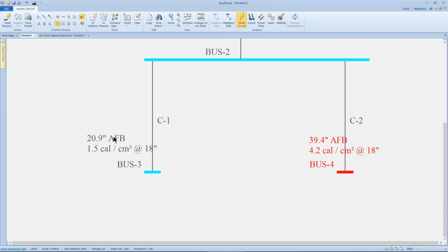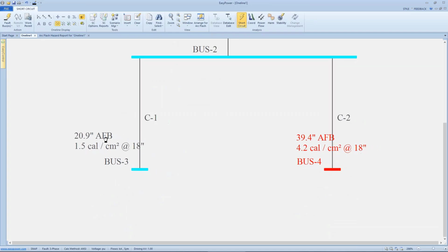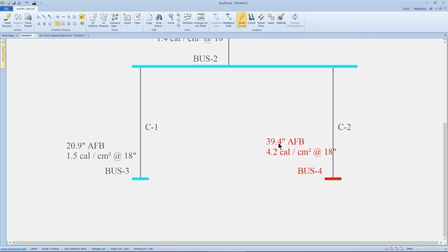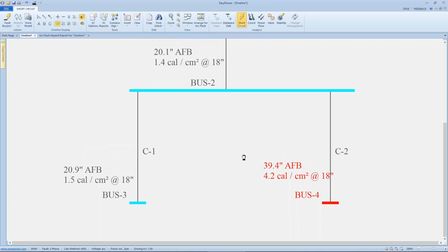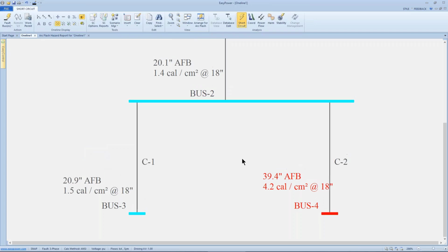If I go down to bus 3, the arc flash boundary is still 21 inches. Incident energy is 1.5 calories per square centimeter at a working distance of 18 inches, so I know I can basically use the same PPE to work on this bus hot. If I go over to this last bus 4, my arc flash boundary has doubled, the incident energy is almost tripled, and now you're telling me I need to put on more PPE because of the elevated energy on this bus. I said, yeah, what are you trying to get at?